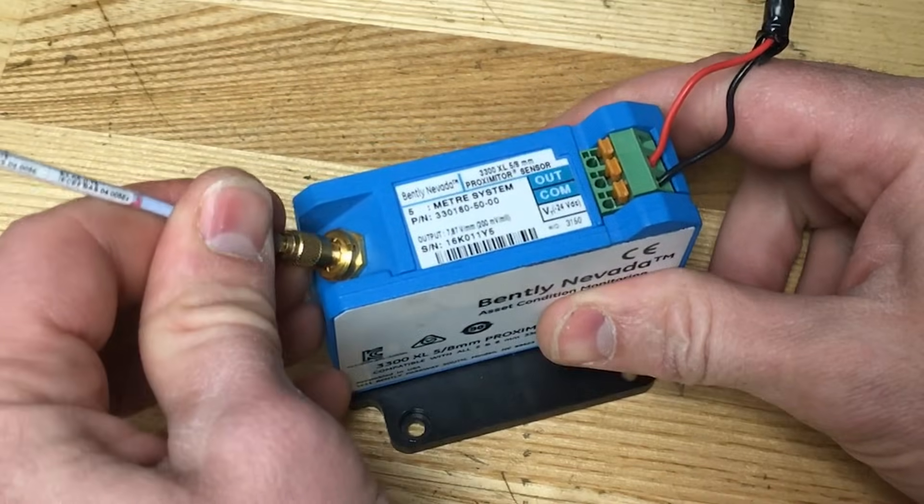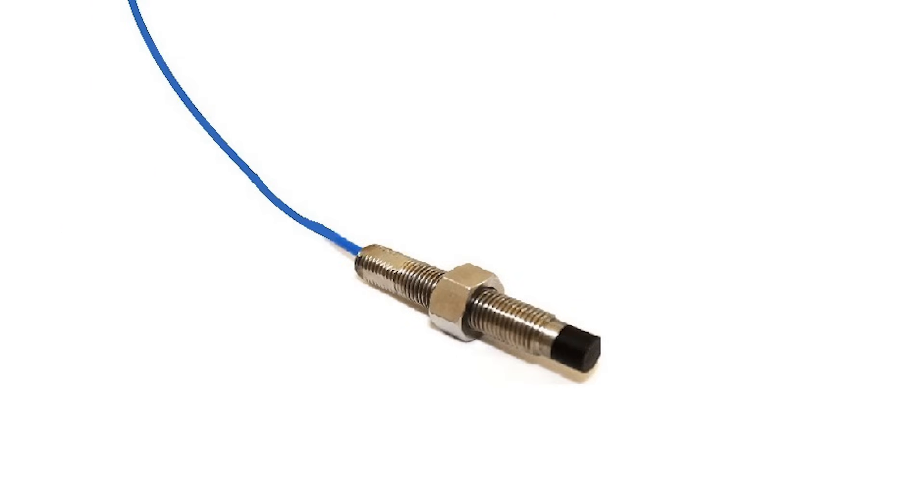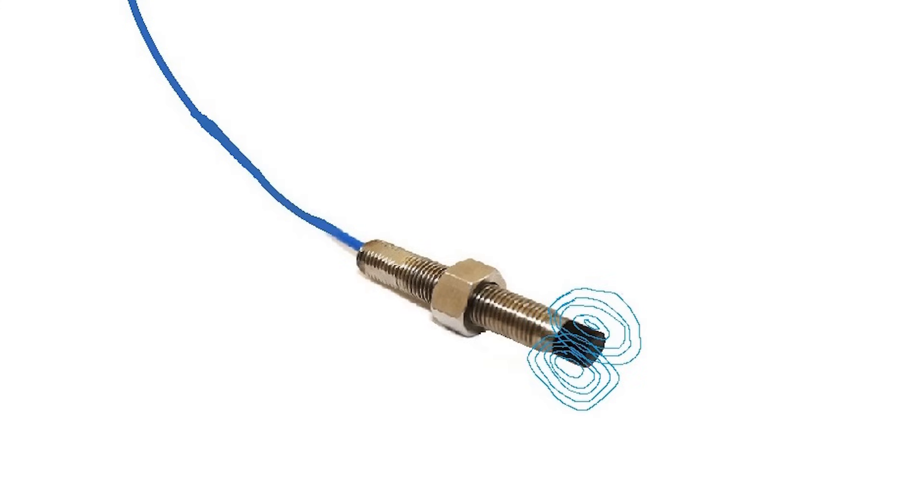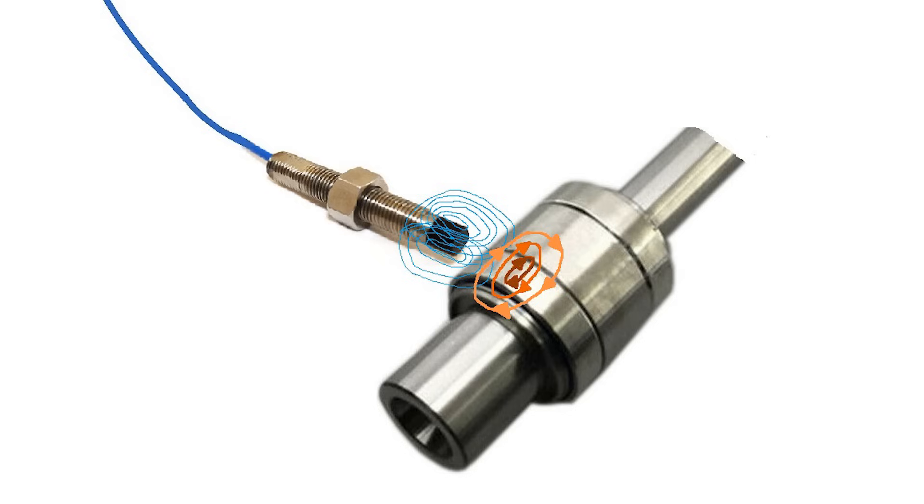The proximitor is responsible for providing an oscillating signal to the coil, which in turn produces a varying magnetic field. As metallic objects move into this field, induction occurs, forming eddy currents.